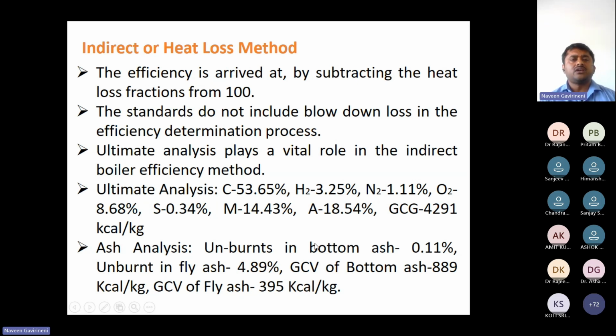This is the ultimate analysis, the ultimate analysis for all. This is a practical one as per my company analysis, which I am supposed to give here: carbon, hydrogen, nitrogen, oxygen, sulfur, moisture, ash, GCV. This is the unburnt fly ash. I already told you, 0.11% bottom ash, so less, and fly ash 4.89, which is a little higher than normal operation. Later we reduced this also. So bottom ash LOI and fly ash LOI.